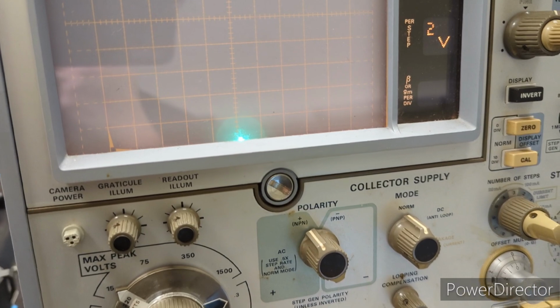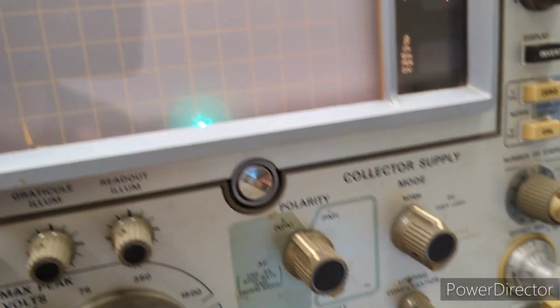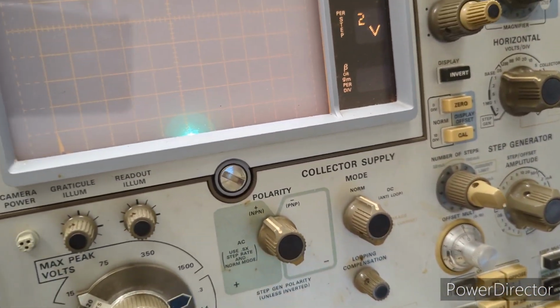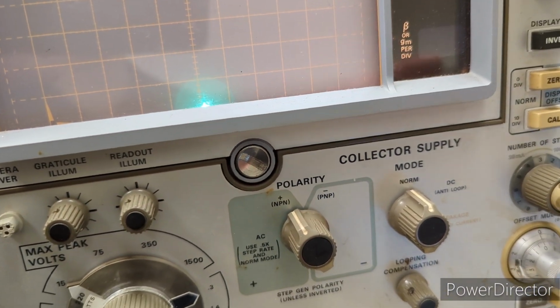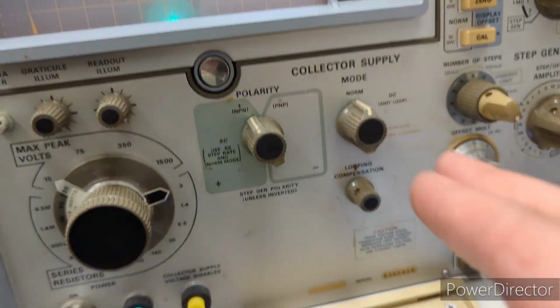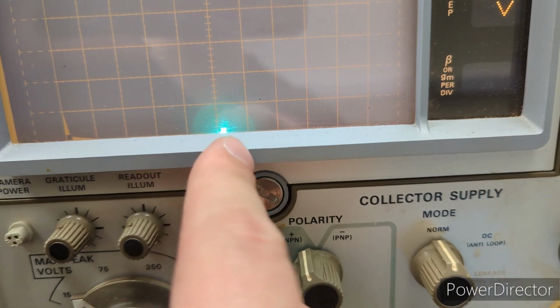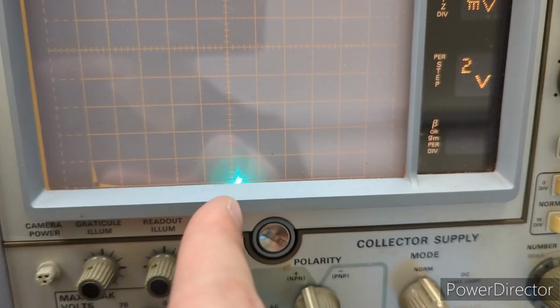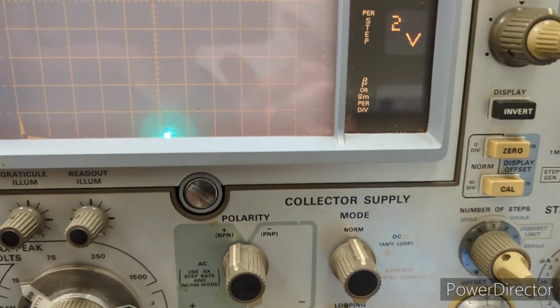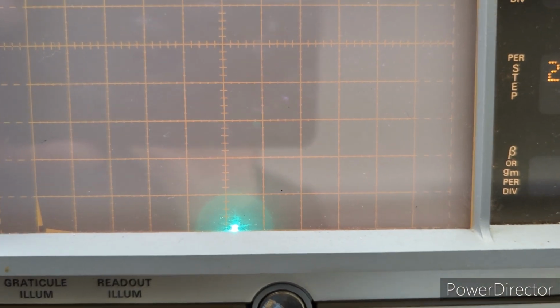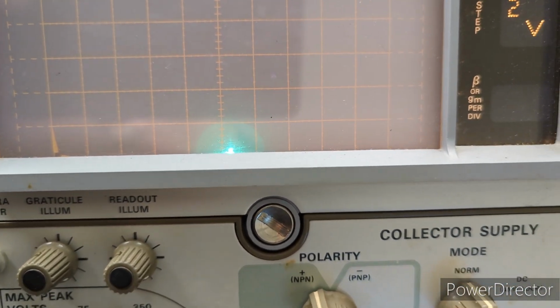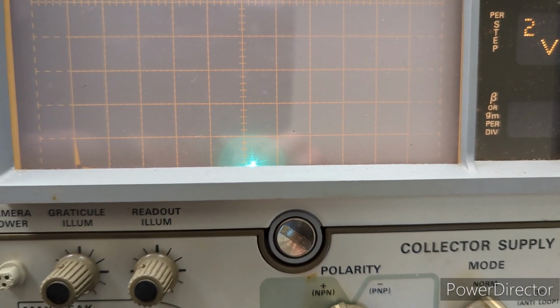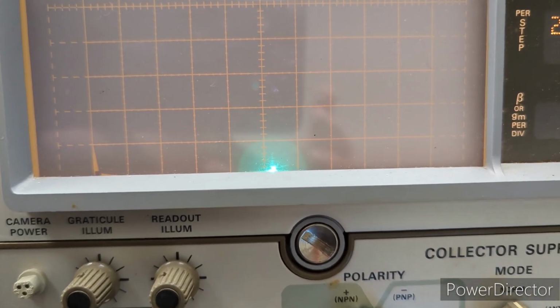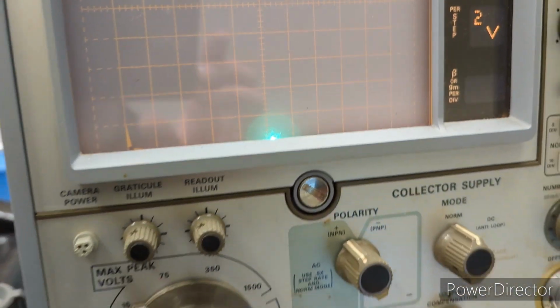Okay, so we just got to another step that required a bit of an adjustment. As soon as I finished saying that this step required no adjustment, you switch the amplitude switch from 0.05 to 2. The trace should be centered horizontally on the CRT graticule, and it was all the way out there. So it actually has drifted a little bit, but by adjusting R97, you can bring it to the center. It's a very finicky pot. Just the slightest adjustment will move it fairly far. So I'm going to have to play with that a little bit more, but I just wanted to note that.